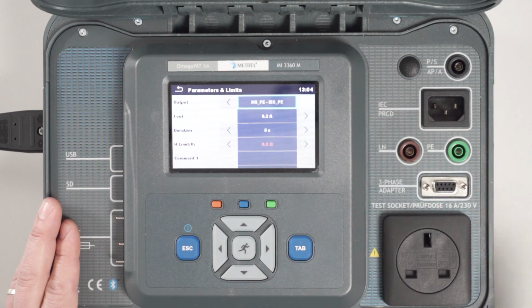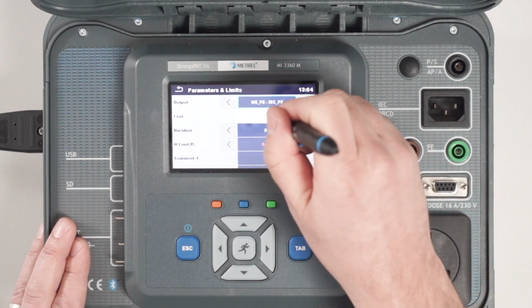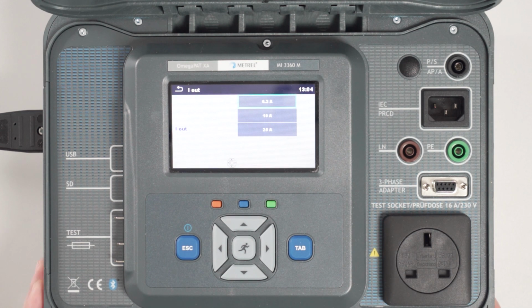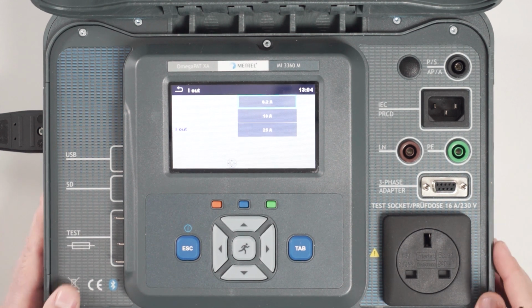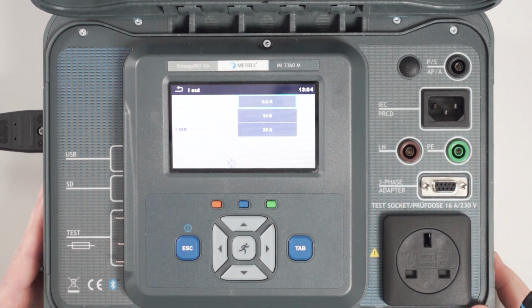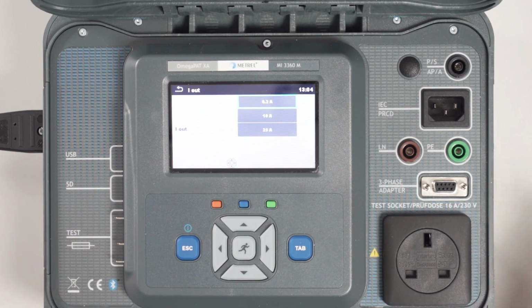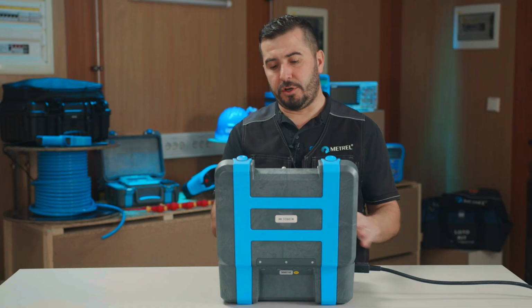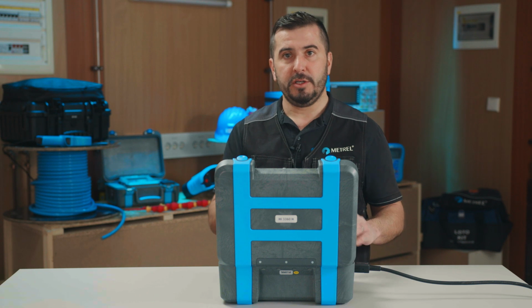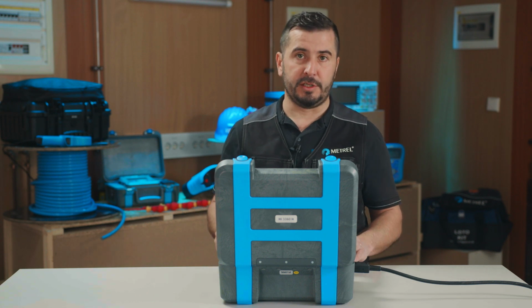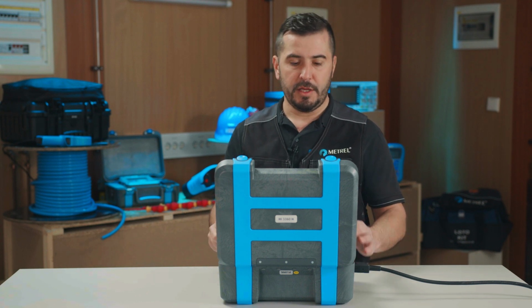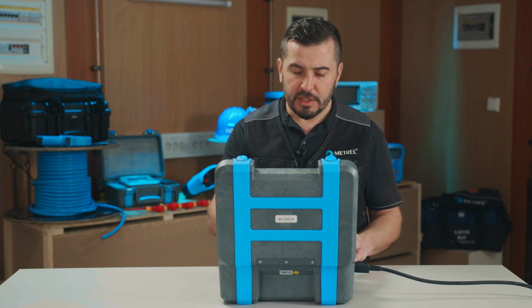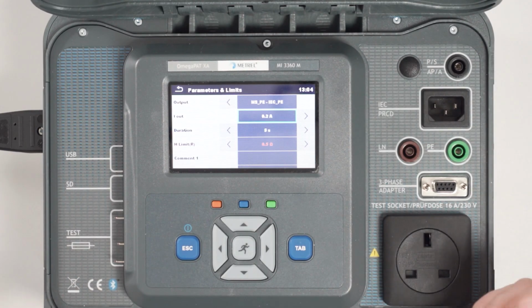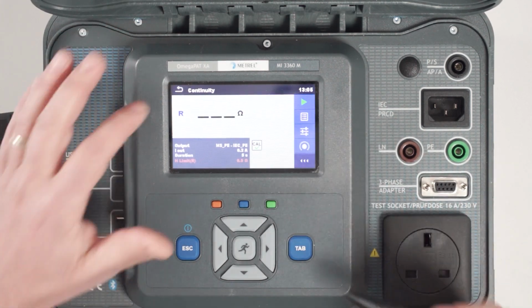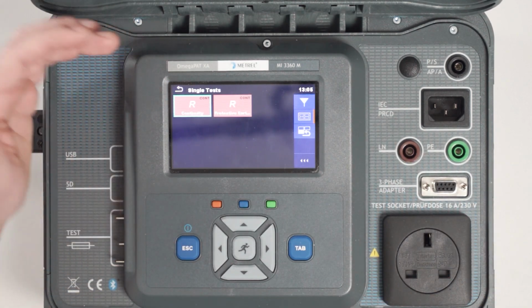Then we can also choose between different test currents. This model has the ability to test with 200 milliamps, 10 amps and 25 amps, though we have also a smaller model which only enables test current up to 200 milliamps. Then we can choose, of course, different duration and different limits. This is about earth continuity.